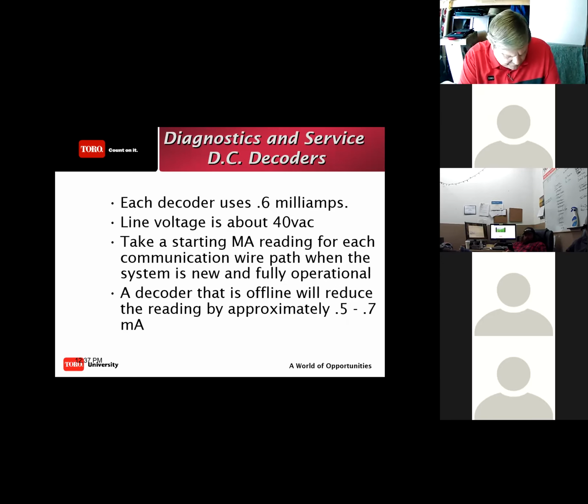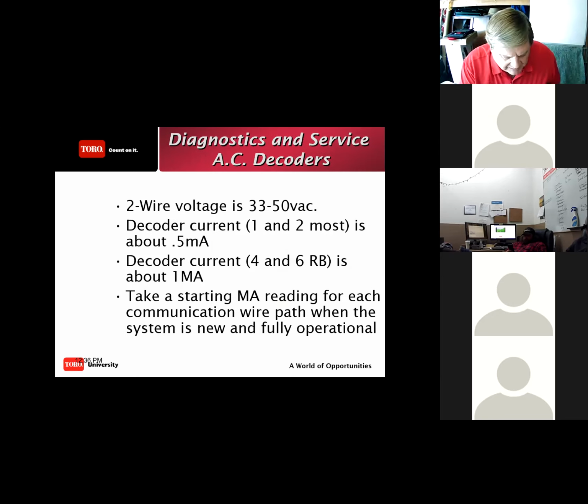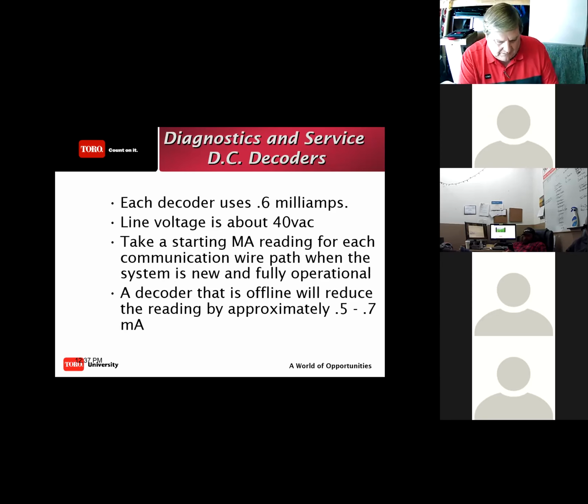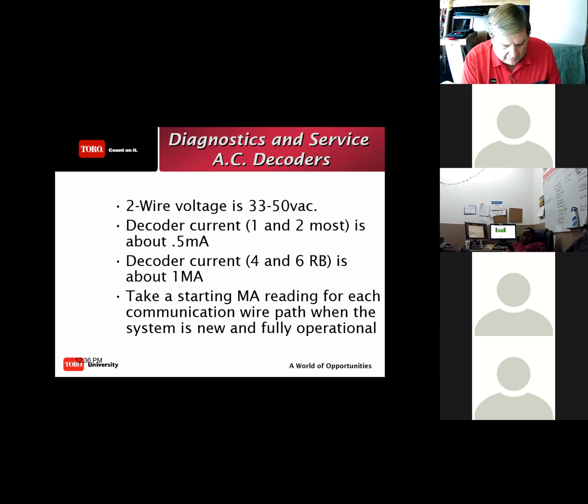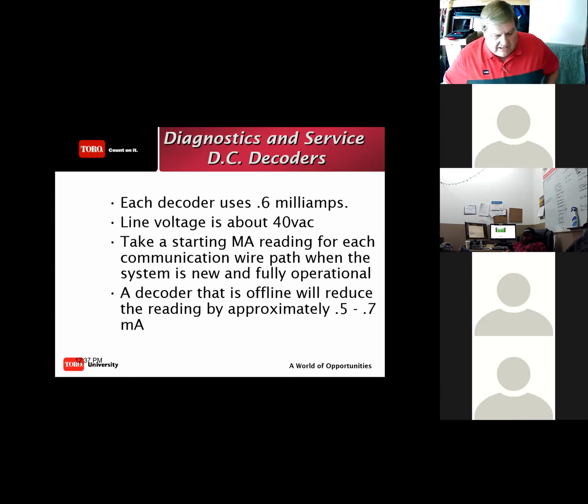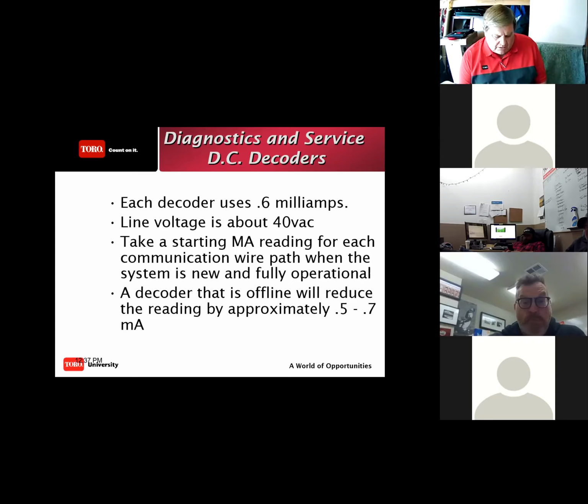DC decoders, there's a few of them out there. If you look at this, a DC decoder has a current draw of 0.6 milliamps. What was the AC? 0.5 milliamps. They're negligibly different. Line voltage 40 volts. Well, this is 33 to 50. I think they're pretty much in line with each other. Whether it's DC or AC, your current draw is relatively the same. And when you're doing troubleshooting on your 2-wire path, the current draw is reading the current draw of the decoder, whether it's turning on an AC valve or turning on a DC valve. The current draw on the 2-wire path is similar.